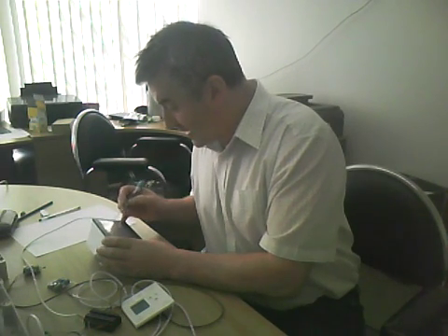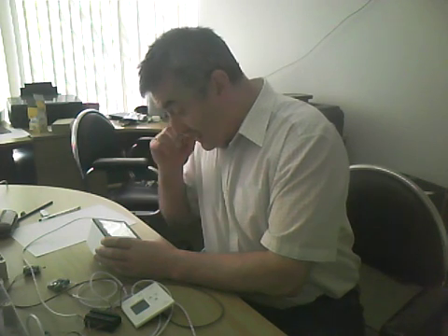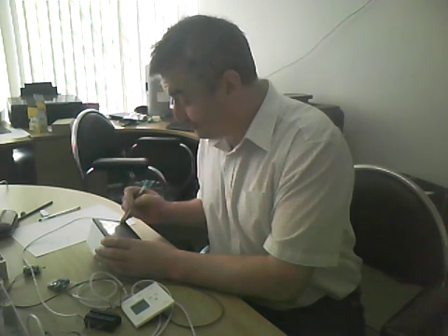Okay, we're finished our test here, and it's in relation to all heating zones on. The main difference, what we're trying to see here, is what's going to happen with domestic hot water when we do that. But we've also seen that a schedule only zone acts a little bit differently as well. We've seen this in the past last test as well.